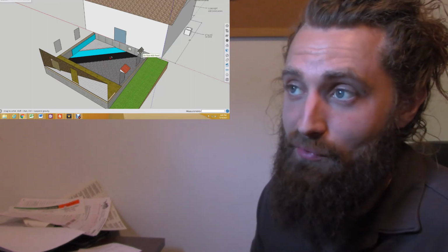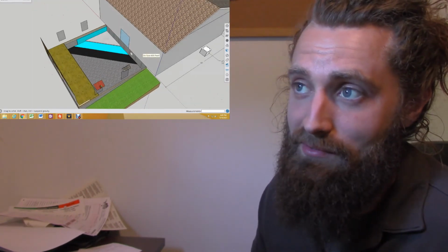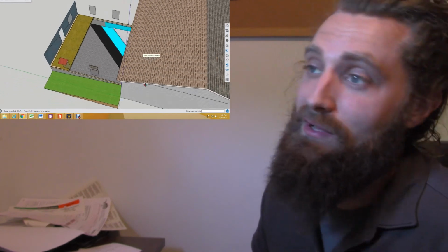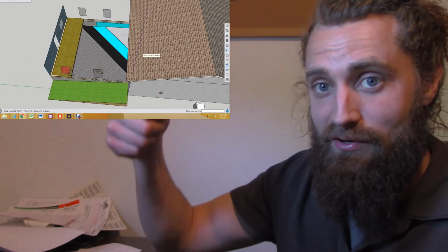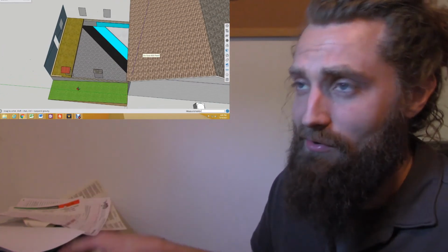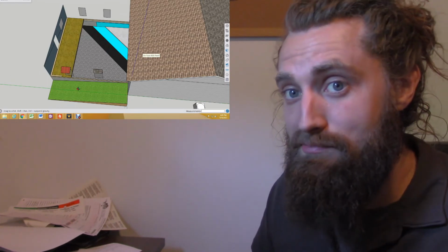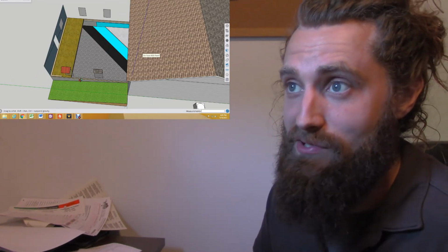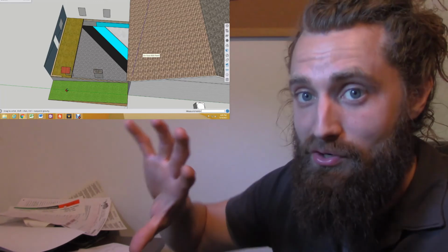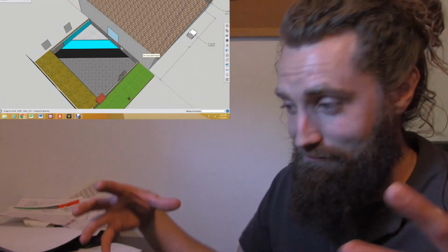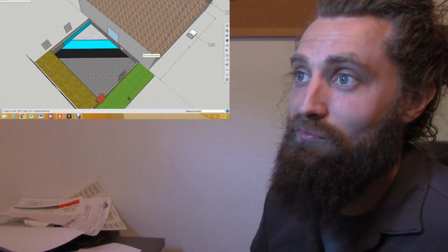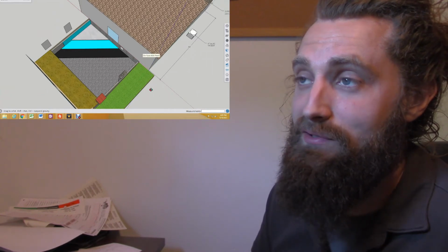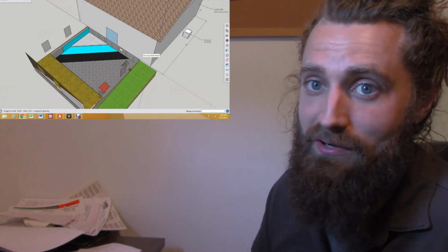And if we look at the blower itself, what's going to happen to it? It's possible you'll see your amperage draw increase. Maybe not a whole lot with 400 CFM, but it's possible. You get more return to that blower, it's able to push more air, you've got more restriction and load on that blower wheel, and it's going to cause the amperage to go up.